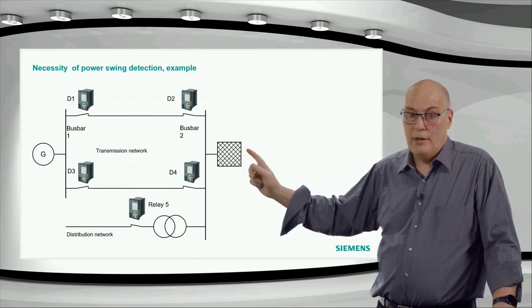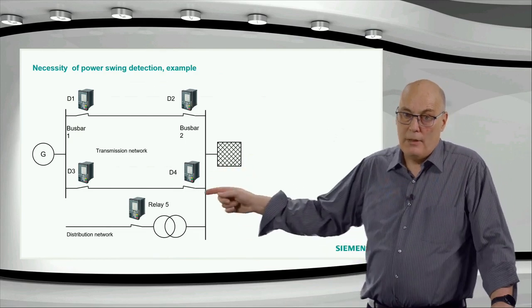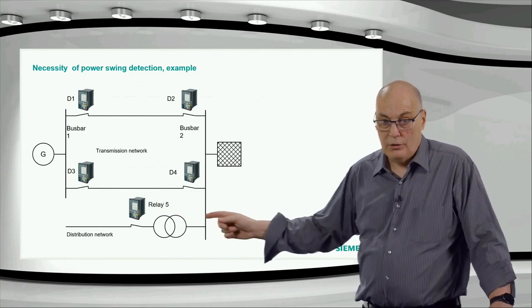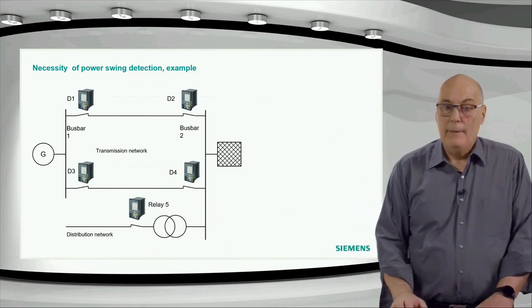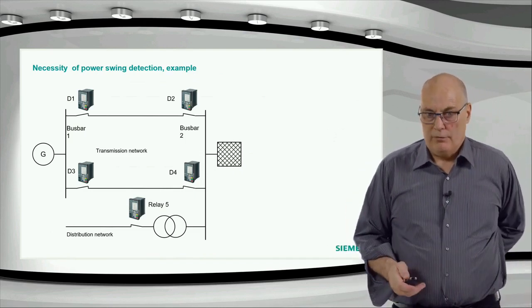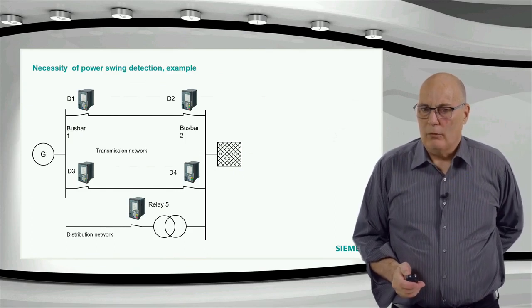This is the load side and somewhere quite remote generation there. And what happened on this bus bar, somewhere in the middle of this transmission system, there was a distribution transformer, and on the LV side of the distribution transformer was a fault, and that fault was not cleared immediately. I think it was some animal on the LV side of the transformer, and it was somehow not cleared properly or it stayed on for a certain time.